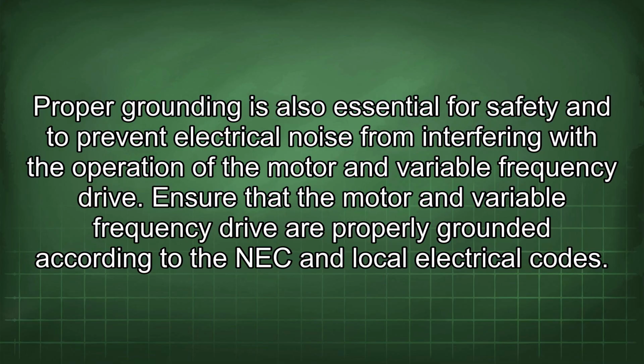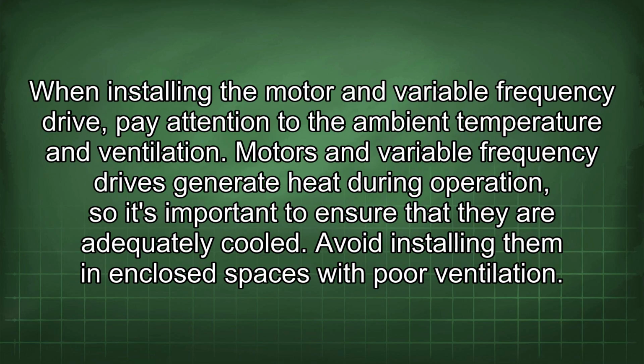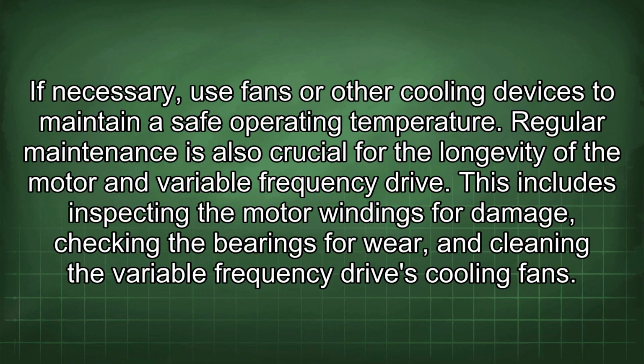local electrical codes. When installing the motor and variable frequency drive, pay attention to the ambient temperature and ventilation. Motors and variable frequency drives generate heat during operation, so it's important to ensure that they are adequately cooled. Avoid installing them in enclosed spaces with poor ventilation. If necessary, use fans or other cooling devices to maintain a safe operating temperature.